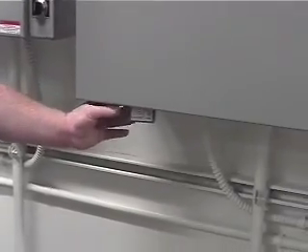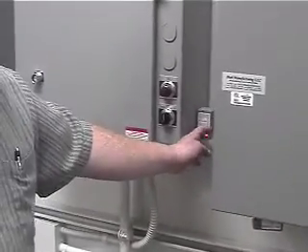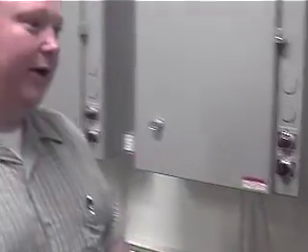And I'll explain the difference here, but what we're doing is there's an ultrasonic level sensor in the cooling towers that measures the level. If the water gets too low, like there's no water in the sump, we actually lock out the pumps from running so you don't run the pumps dry. And so that is a safety there that won't allow the system to run if there's no water in it.